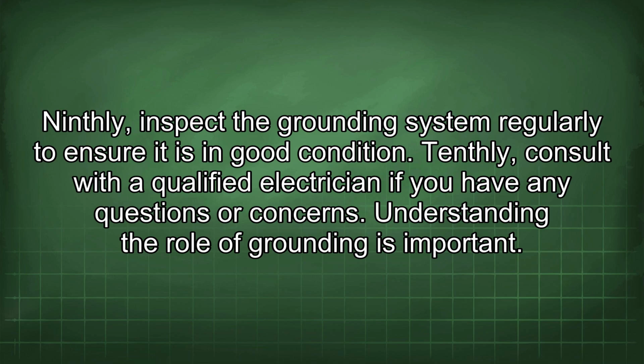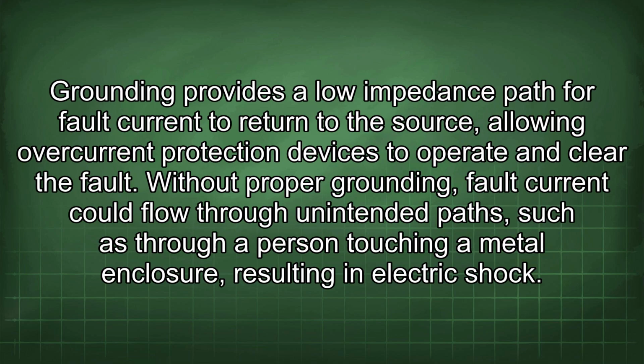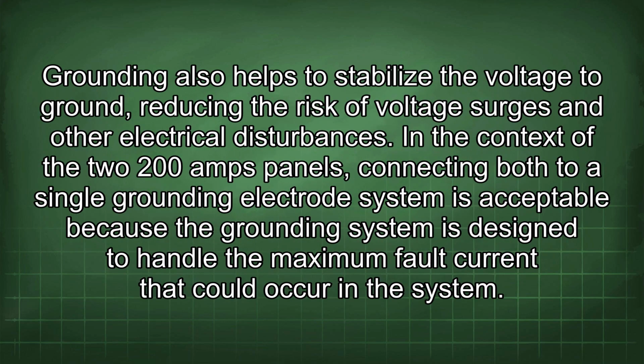Understanding the role of grounding is important. Grounding provides a low impedance path for fault current to return to the source, allowing overcurrent protection devices to operate and clear the fault. Without proper grounding, fault current could flow through unintended paths, such as through a person touching a metal enclosure, resulting in electric shock. Grounding also helps to stabilize the voltage to ground, reducing the risk of voltage surges and other electrical disturbances.